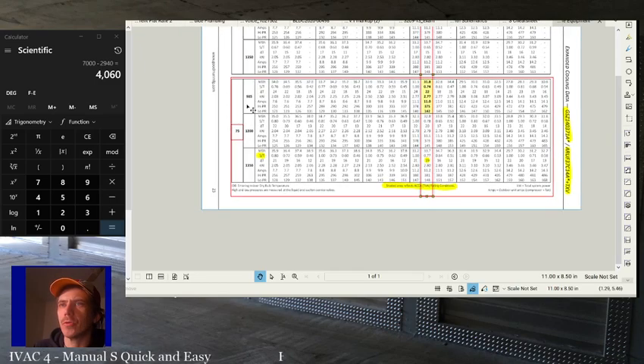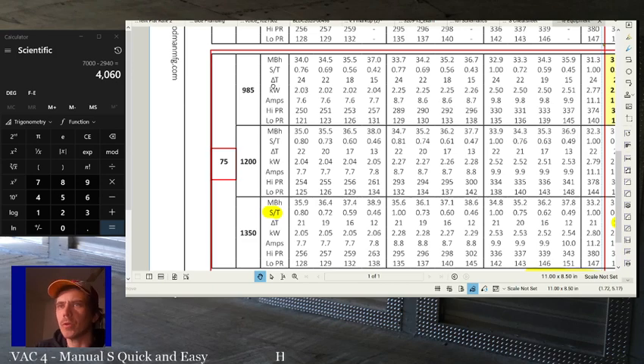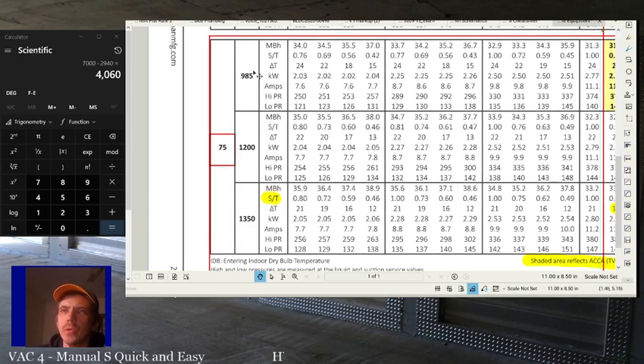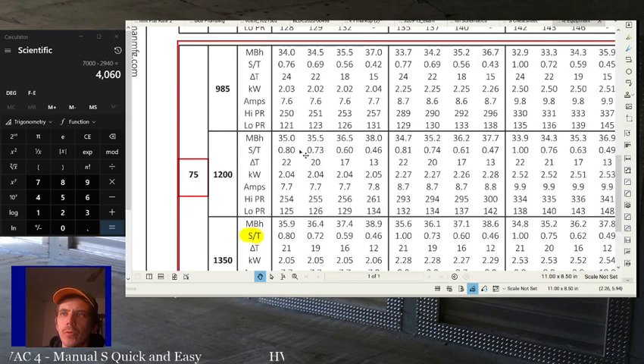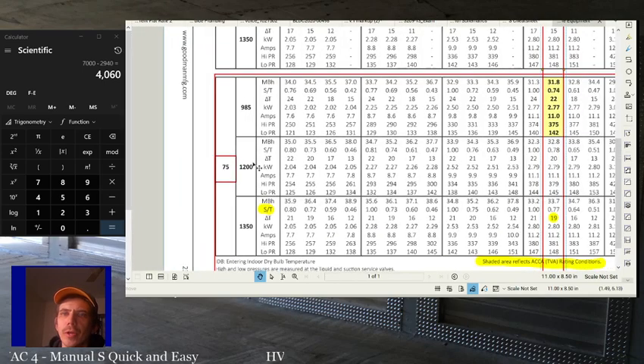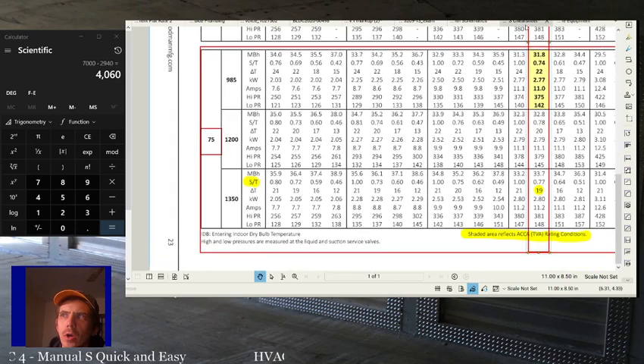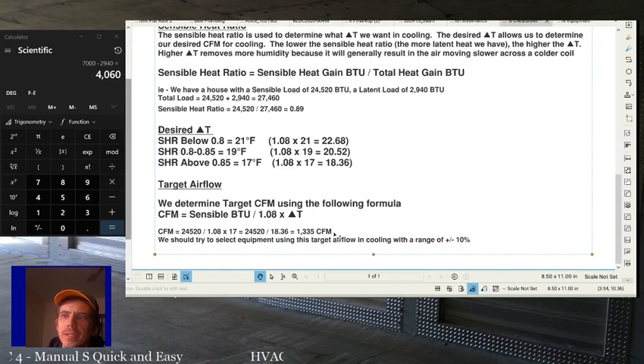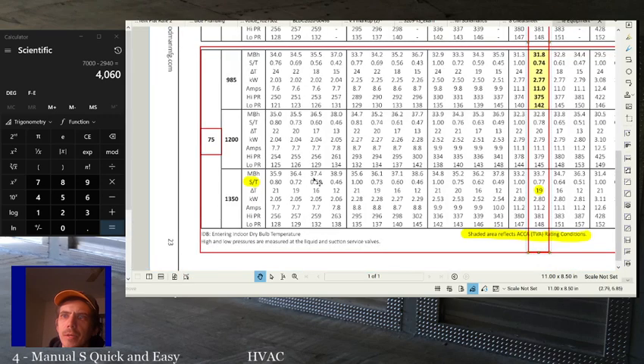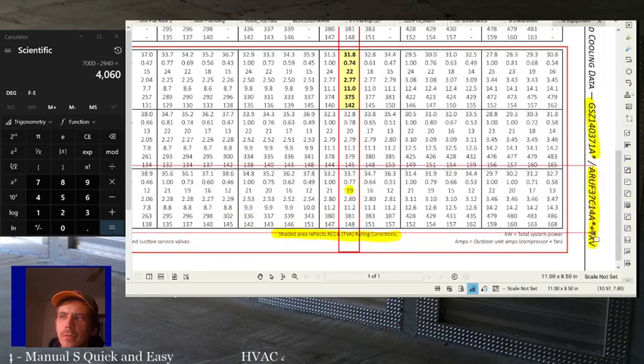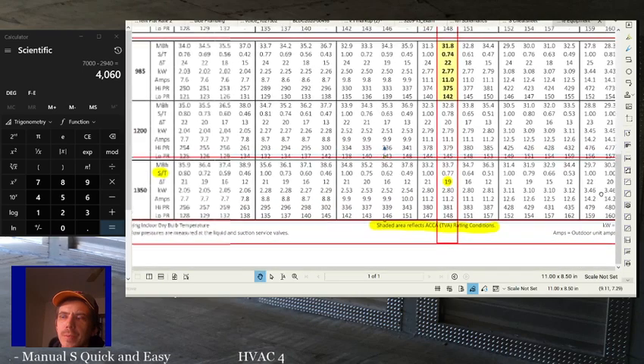Now we have to narrow these rows down. To narrow these rows down, most cooling equipment is going to give you 3 options on airflow. This is kind of like your low airflow, your medium airflow, and your high airflow sides. So you pick the one that's closest to your target airflow. Our target airflow was 1335 CFM, so we're going to pick the airflow at 1350 for now. Right, so we're going to be in this bottom one.